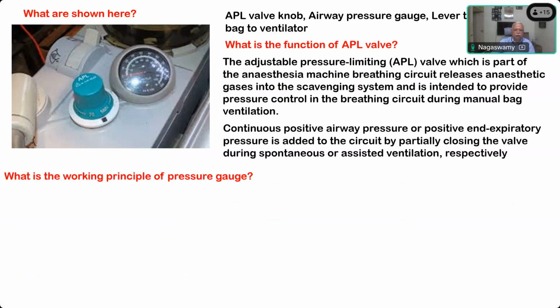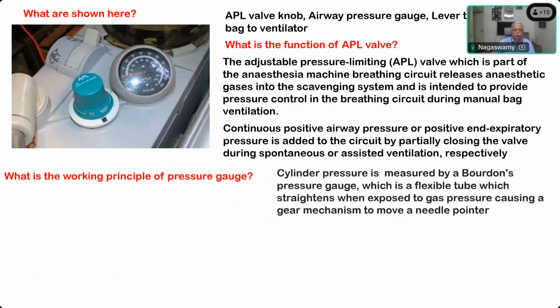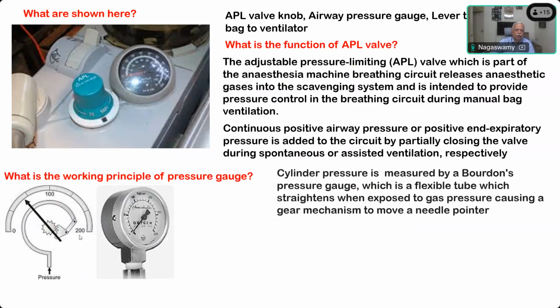What is the working principle of the pressure gauge? Cylinder pressure is measured by the Bourdon pressure gauge, which is a flexible tube which straightens when exposed to gas pressure, causing a gear mechanism to move the needle pointer. So this is the picture to show you how the gas pressure enters the pressure gauge, and once it goes, it tries to straighten this malleable tube, and this pointer will move showing the pressure inside.